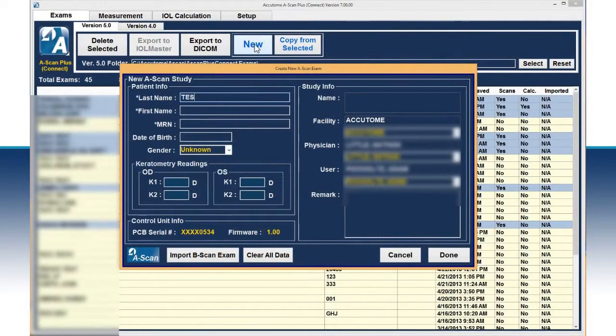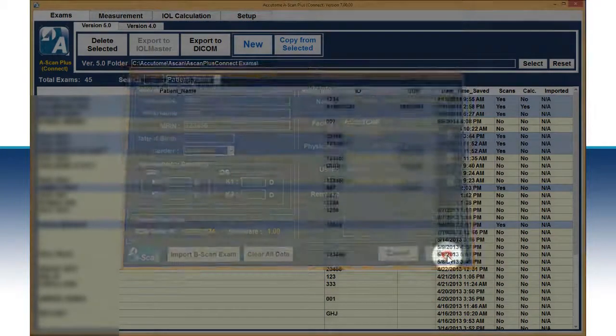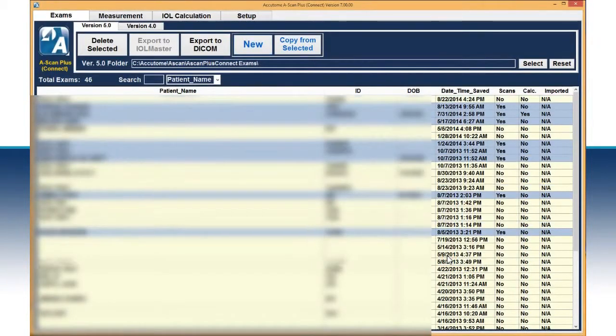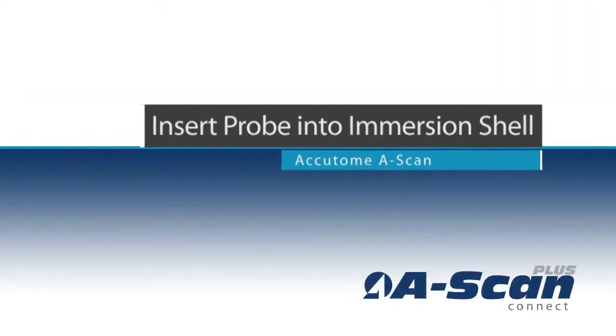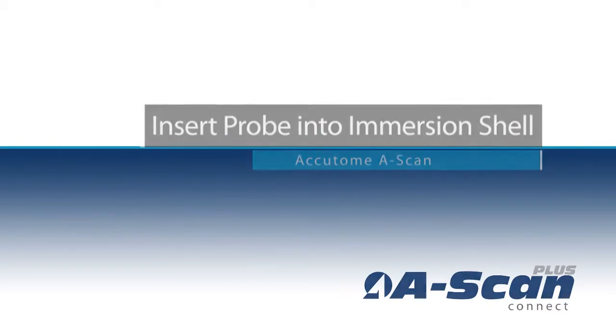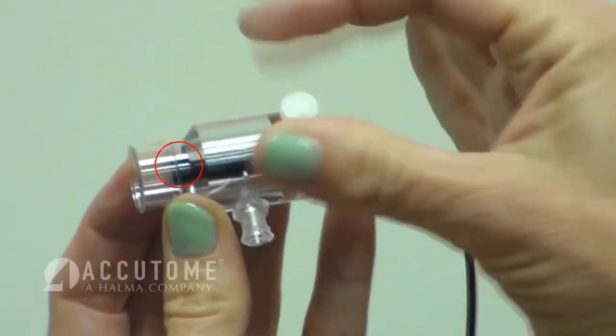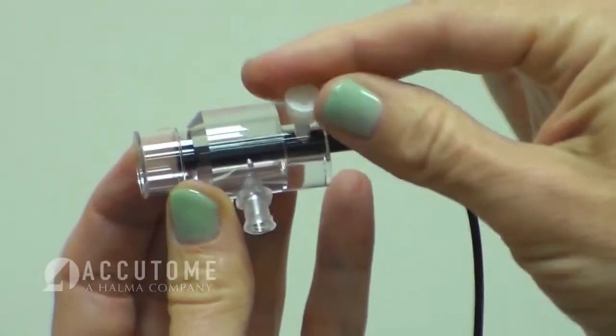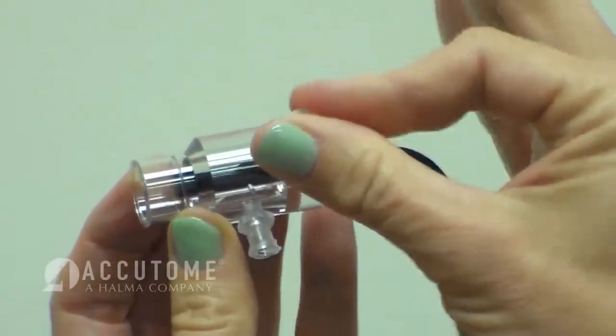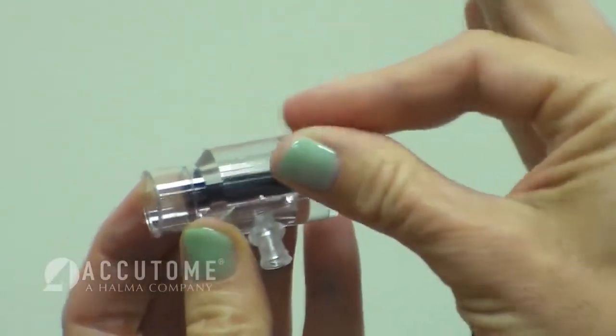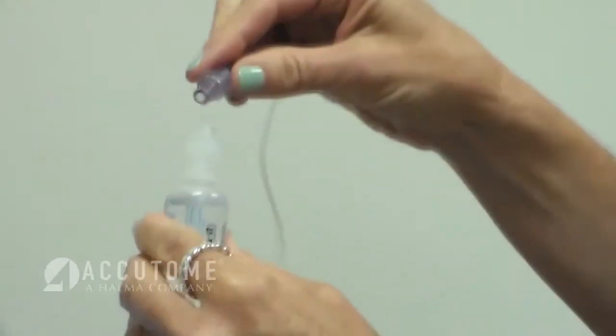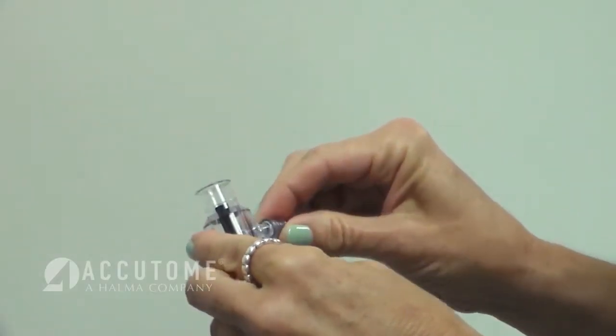Fill in the resulting screen with all of the patient's demographic information and press the Done icon at the bottom right. The software will automatically take you to the measurement screen. To start a measurement, insert the probe into the immersion shell to the proper depth. It is important to not place the probe past the scored line. Lightly tighten the set screw to fix the probe in place. Connect the tubing and balanced salt solution to the shell.